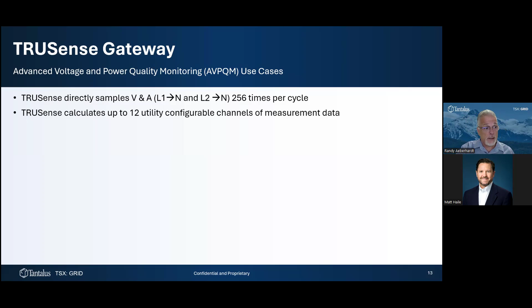For each of those channels, when you configure it, you configure the measure, the periodicity, and the method—whether you're using RMS, min, max, average, peak to peak, or whatever it is. Then you configure the destination, which can be nowhere if you're just feeding a trigger, or it can be TrueConnect Insight, or TrueSync if you're delivering this data directly to your SCADA system.